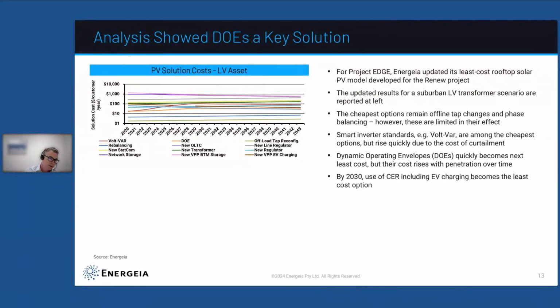I will draw your attention to the logarithmic scale here. You've got the option of volt var, which is a smart inverter standard that basically if voltage gets too high, it folds back and either changes the power factor and or curtails the amount of real power being exported. Now that increases over time because of the level of penetration and the level of curtailment that goes with it. And so it starts to creep up and is no longer really the least cost option. You see what comes in after that is the dynamic operating envelopes.